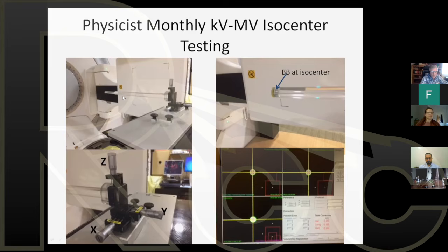Many times this is called the Winston-Lutz test. Elekta provides this with their linear accelerator. This is part of the package. When you buy an Elekta linear accelerator, you get this imaging device that the service engineer will use, but I encourage the physicist to use it also on a monthly basis. At the end of this rod is a ball bearing. You see it right there. And there's a cross here, both in the sagittal plane and in the up and down, left to right.